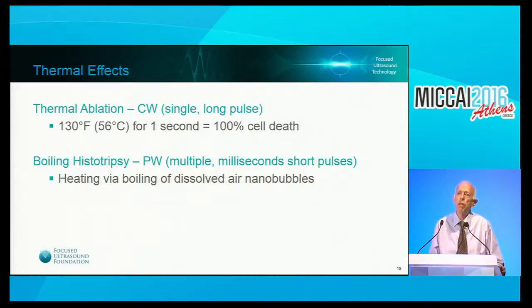And it's enough to hit the tissue at 60 degrees for less than 1 second in order to completely destroy the tissue, to induce immediate cell death. It's like freezing the tissue in time and basically deactivating all the biological processes inside it. This is, by the way, why there is very little inflammation when treating with focused ultrasound relative to other ablation techniques like laser or RF that rely on conduction. Here we don't rely on heat conduction. It's an immediate effect in the area of the focal zone.